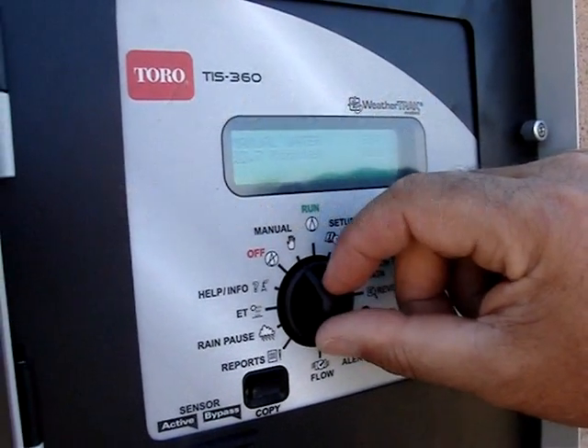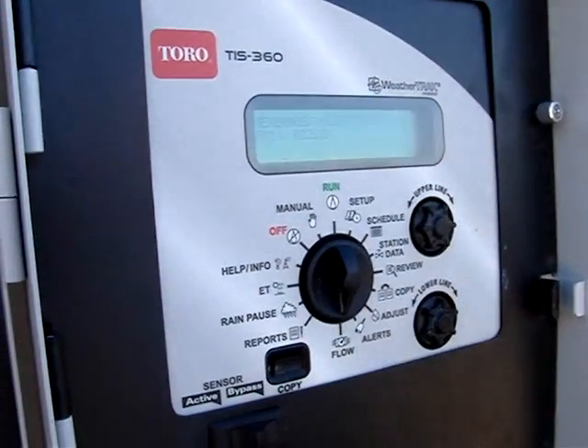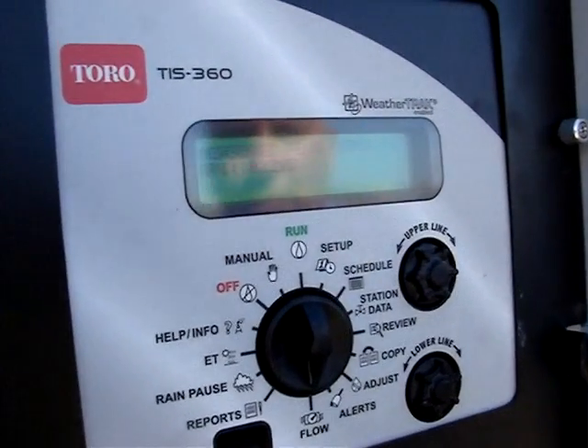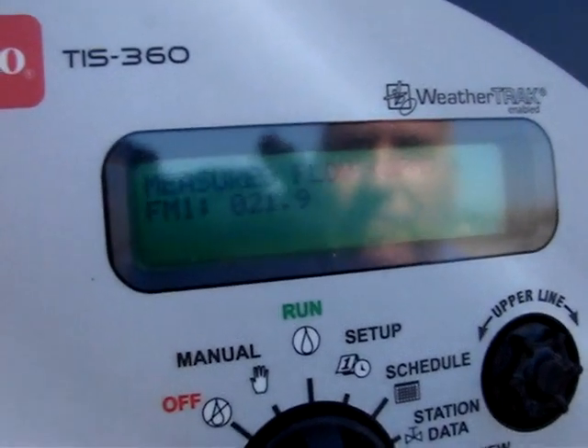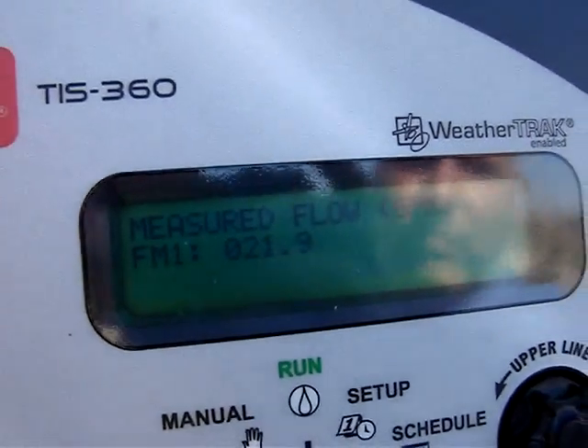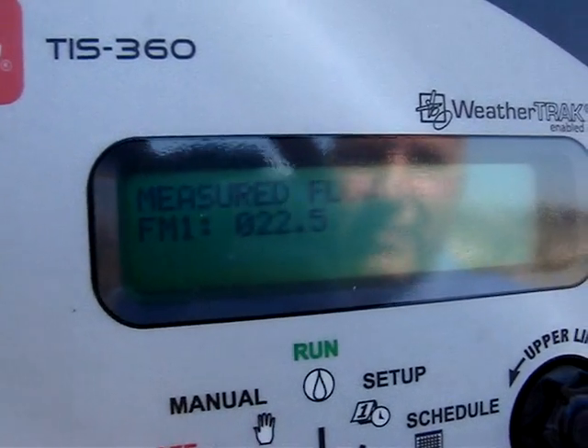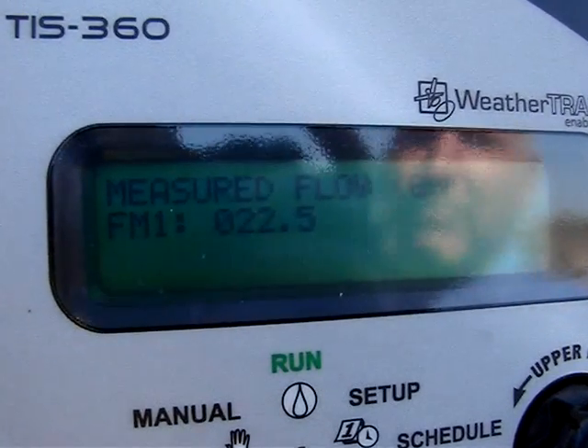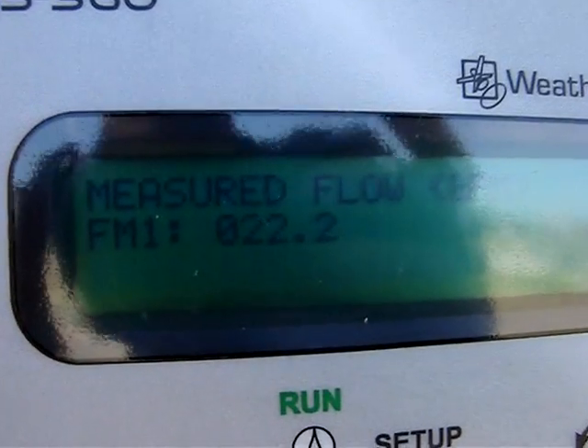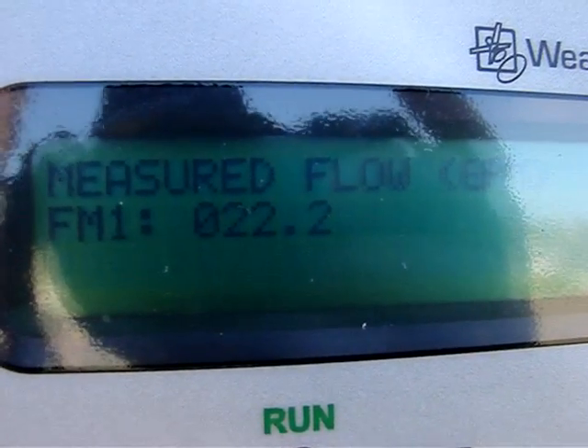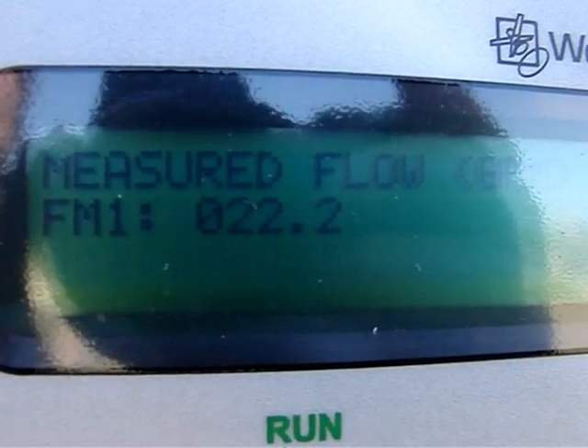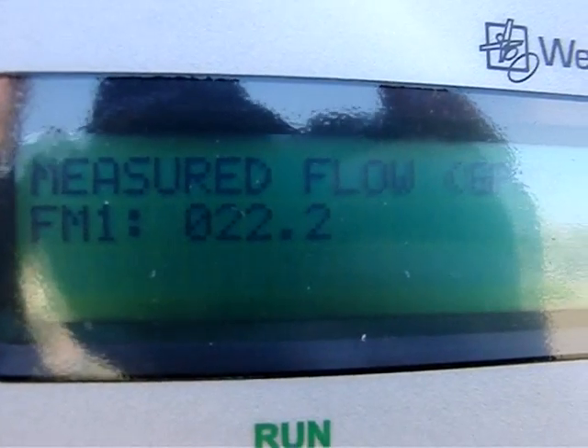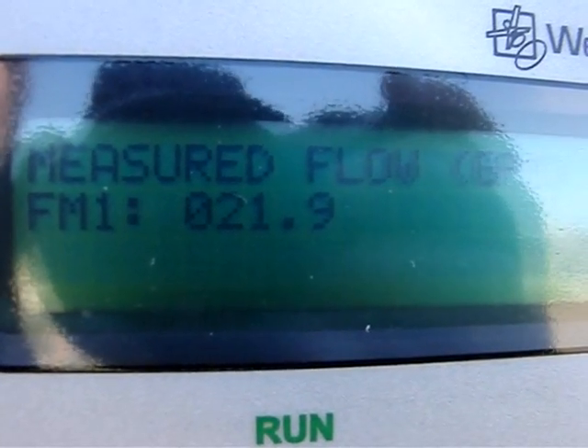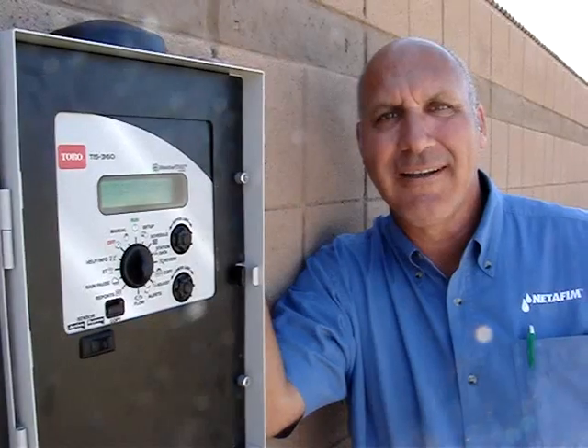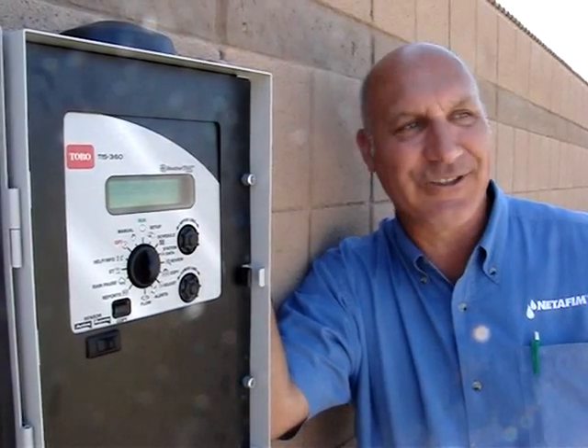Okay, we turned off the water, now we just turned it on again, and we're going to let it balance out, and then you will see that we are right around the same flow rate, 21.9 to 22.5 gallons a minute. And that gives us the ability to put very tight alarms on this clock and have confidence that we're not going to get false alarms. Yeah, let's go sell some water meters.